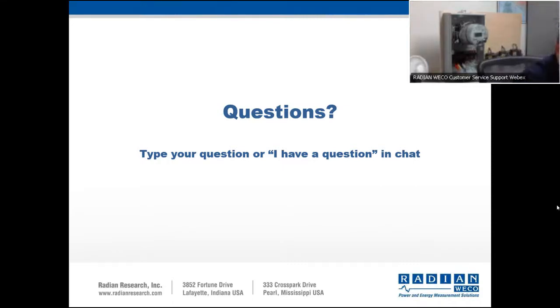Running demag changes CT ratio, how much of a change? It varies depending on how magnetized that CT is, if it is at all, or two, how that CT affects things when burden is applied.